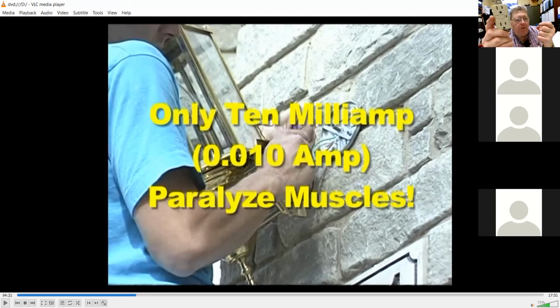And they call it GFCI. Who knows what the 4 letters of GFCI mean? Ground fault circuit interrupter. That's right. Ground fault. Now we talked about that. And when we say ground fault, we say that some of the current in that circuit did not return through neutral back to ground. It was not a complete circuit and there was some missing stuff, missing amps, coming back that should have been on that neutral.